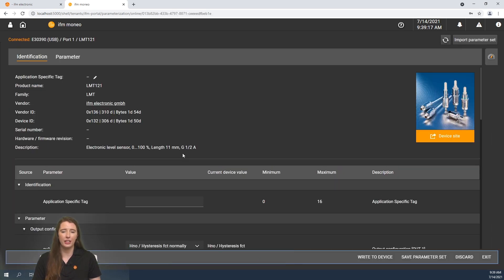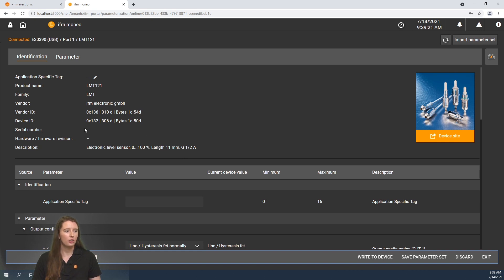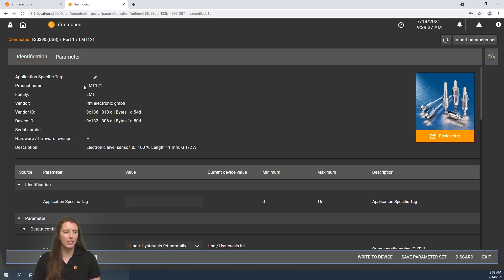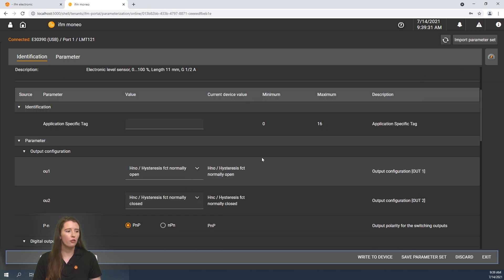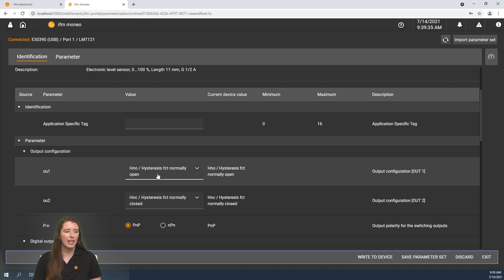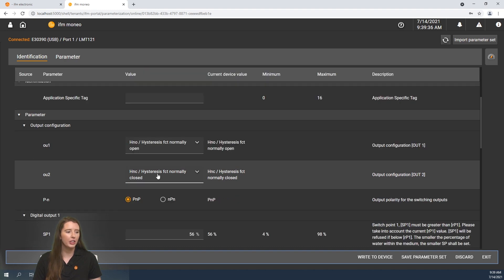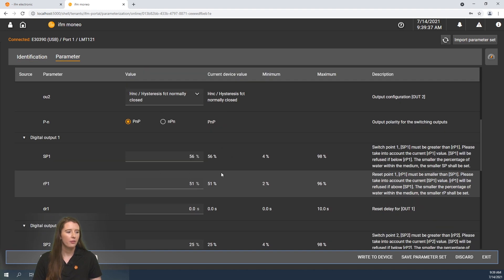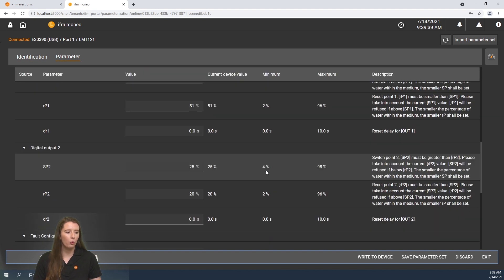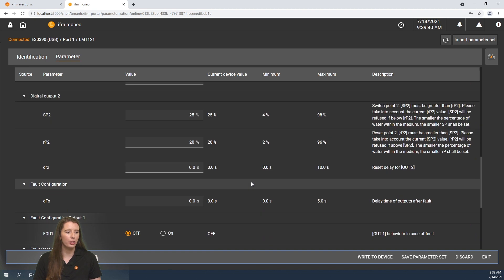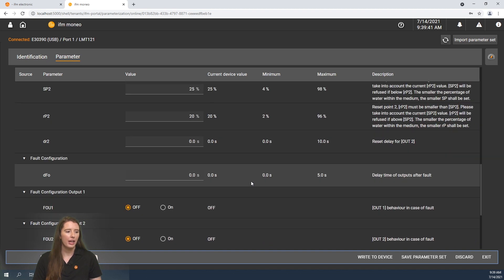I will then click on this sensor and it will begin to pull in the identification information and parameters that I can change for this sensor. Here you can see the vendor ID and device ID of the LMT 121, the name of the sensor that is pulled in as well as the description of the sensor. If you scroll further down you will see the different parameters that you can change such as the output configuration, the set points for output 1 and output 2, as well as any fault and delay configurations that you want to change.